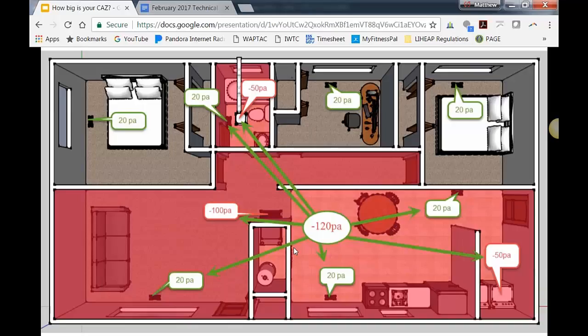No, I think we did good. I just always want to point out to the guys, remember that supply duct leakage out of the envelope is exactly the same thing as an exhaust fan, and you're talking large CFM numbers. Anytime you have supply duct leakage out of the envelope, that's going to dramatically increase your depressurization in the house. And the weird thing we found was the swamp cooler in the bedroom window.